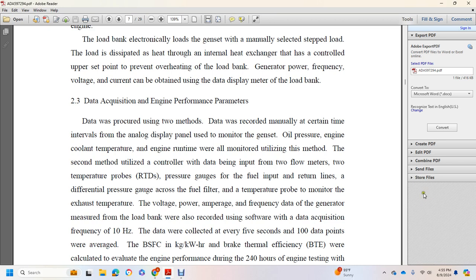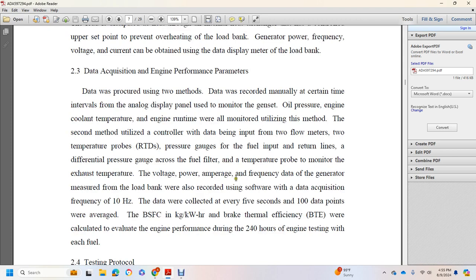The second method utilized control of the data being input with the two flow meters, two temperature probes, and pressure gauges for the return lines, the differential pressure gauge across the fuel filter, the exhaust temperature probe, and the voltage, power, amperage, and frequency. Data of the generator measured for the load bank was recorded using software with a data acquisition frequency of 10 hertz. The data was collected every 5 seconds, and 100 data points were averaged.